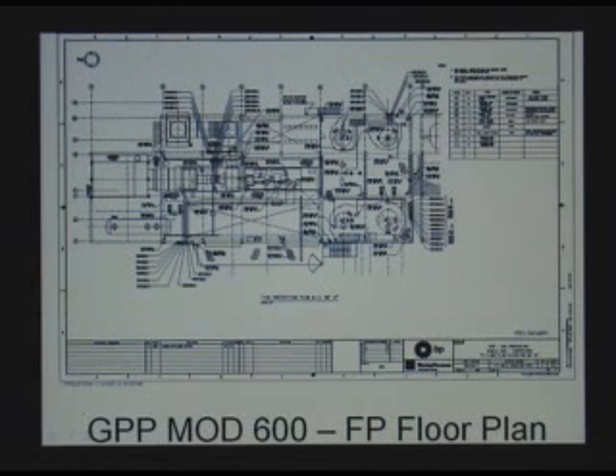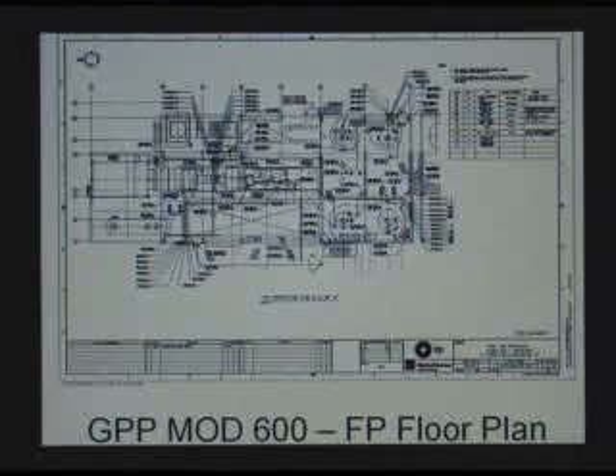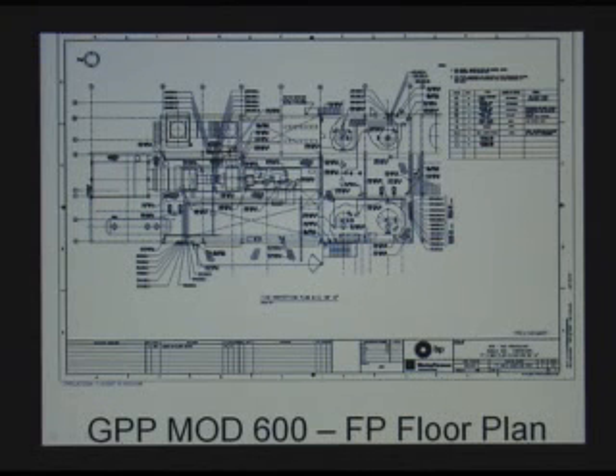And not only that, we provide flame detectors. You've got flame detectors here, flame detectors all over the place, so that in case there's a fire, they can see it. You can't see all the way there, but because of all the equipment we have here, it might block the view of these detectors, so we provide them all around the modules. After that, we do a 3D review to see whether there's any blockage. We also have a pull station at every door. So if there is a gas release, the pull station can be energized.